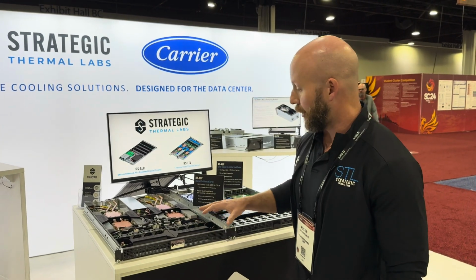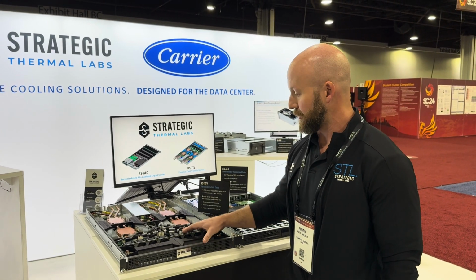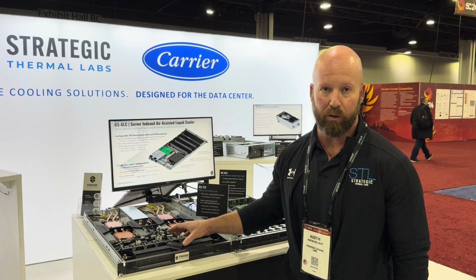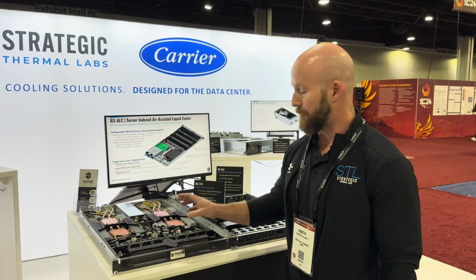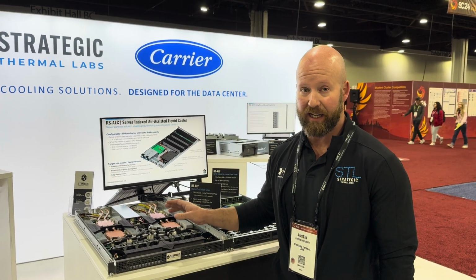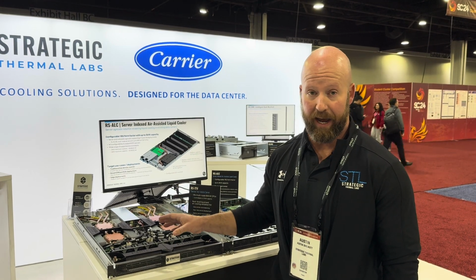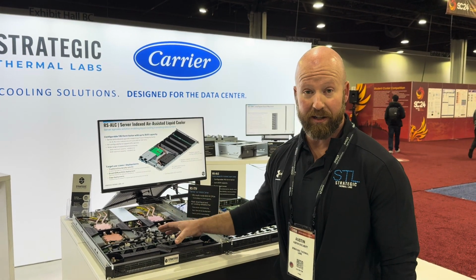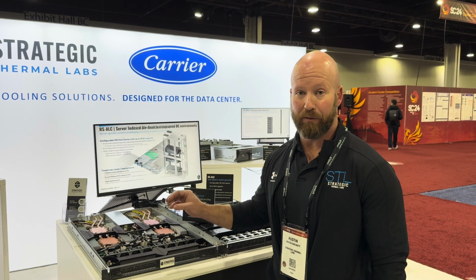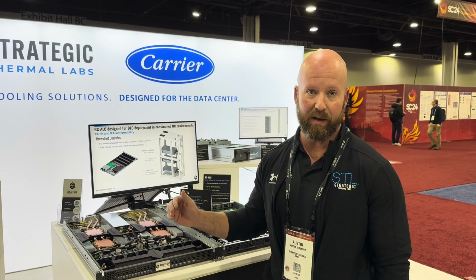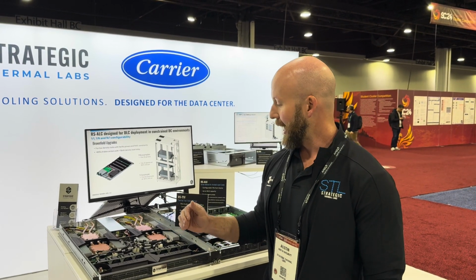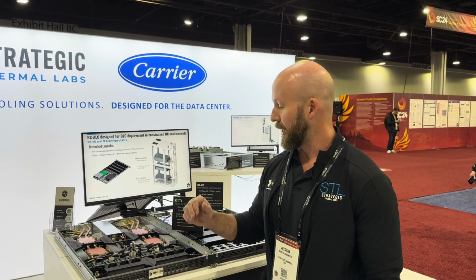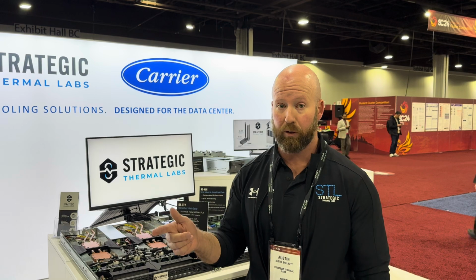First up, I want to show you our thermal test vehicle server. This test vehicle server was designed to emulate the liquid-borne and airborne heat load profiles of the popular half-width, two-socket CPU compute server today. We have the capacity with this device to throttle up heat for CPUs and memory and NVMe devices independently of one another and emulate the heat profiles of those devices so that we can not only validate cold plate liquid performance, but also rack level liquid performance for things like CDUs and manifolds or row-based cooling solutions, in addition to rear door heat exchangers.